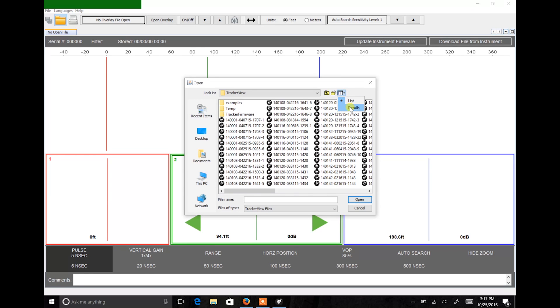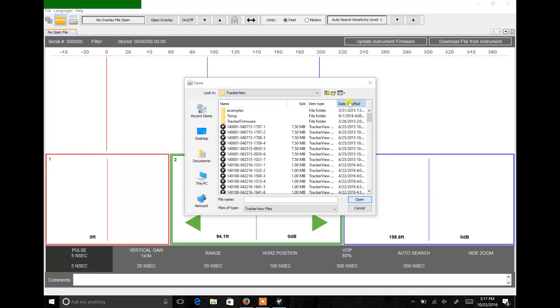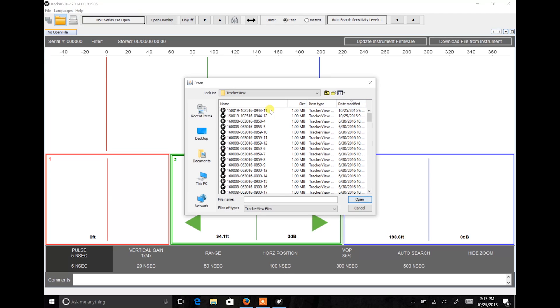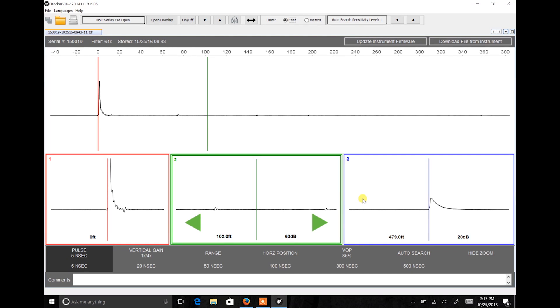By going to the end of the cable and testing in the opposite direction, you place yourself and the TDR much closer to the fault, making it easier for the TDR to locate.